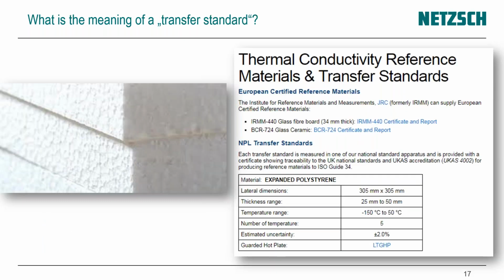So some of you may have heard about a so-called transfer standard. There are also transfer standards available in the market, for example, from NPL. They offer EPS board as a transfer material in lateral dimensions of 300 times 300 millimeters and a thickness range from 25 to 50 millimeters. That comes from the reason that during a calibration, the calibration material should have similar thermal transport behavior to the sample you want to check later on. And this is the reason why sometimes it makes sense to make a calibration with a thicker material.